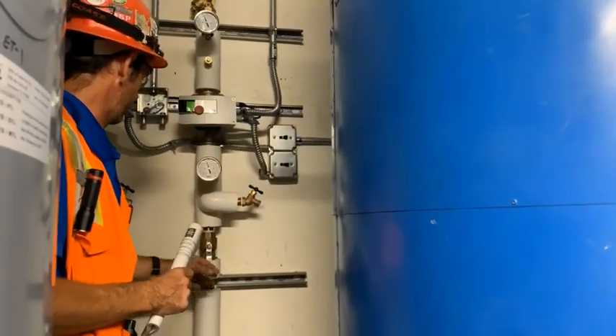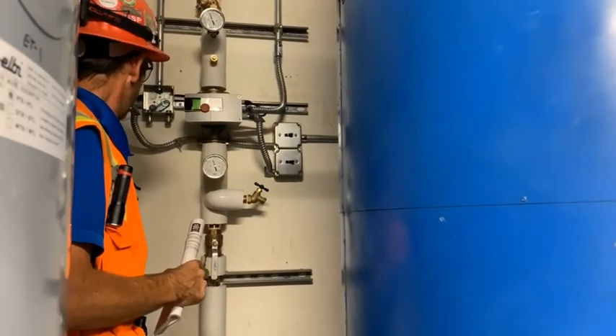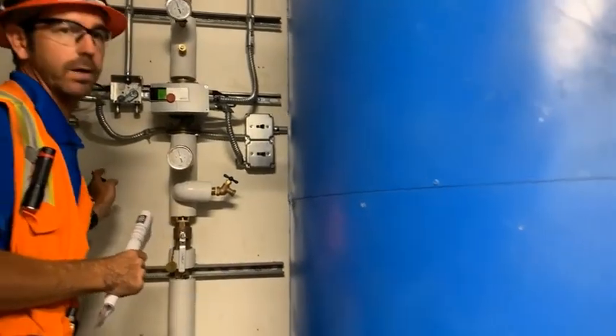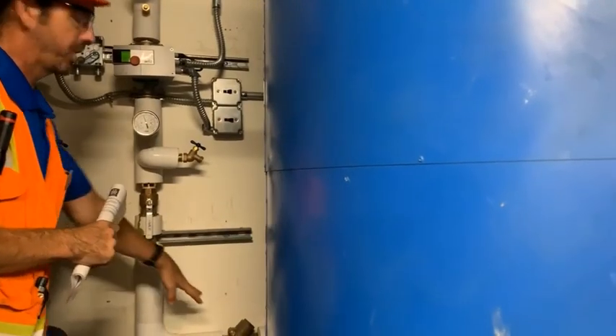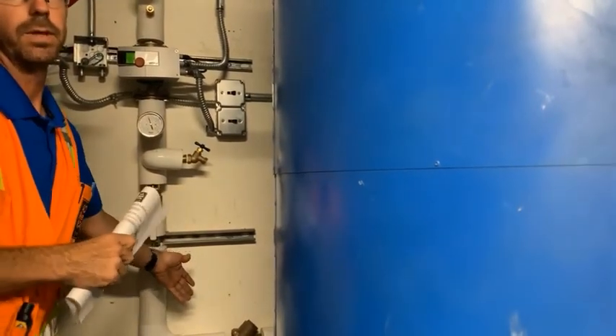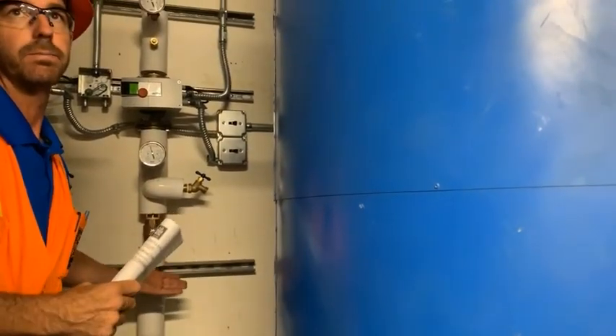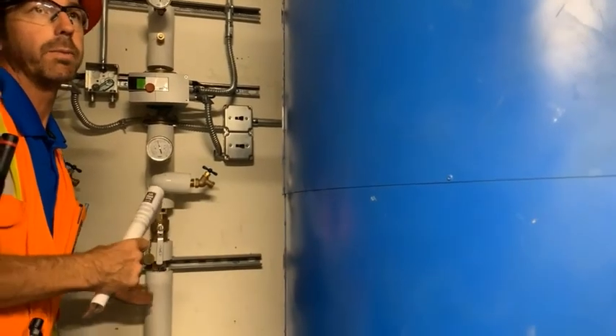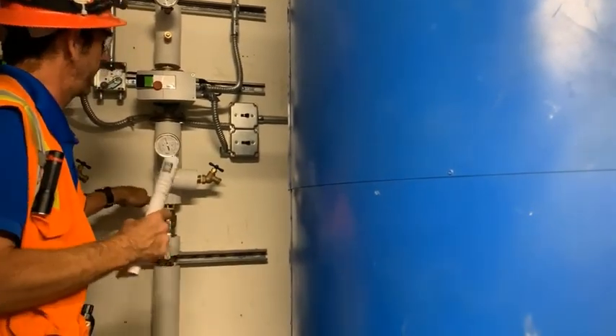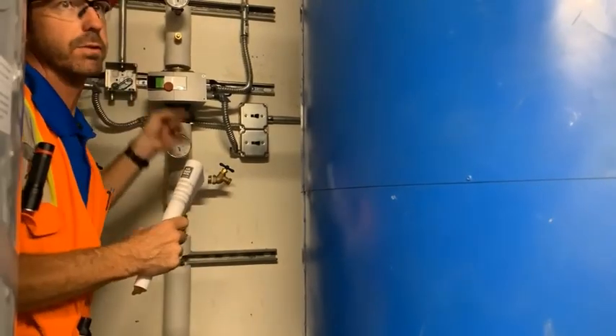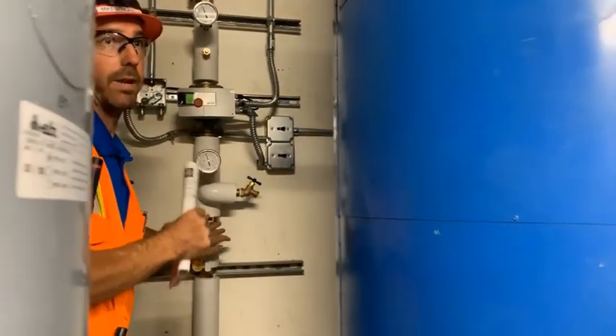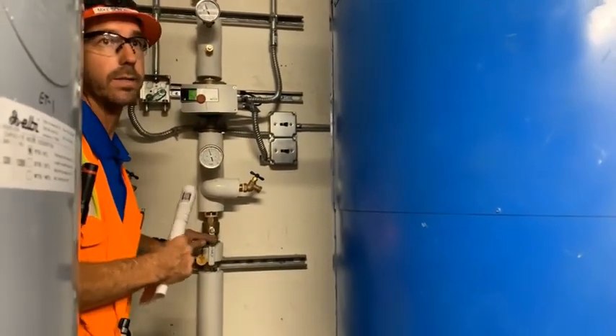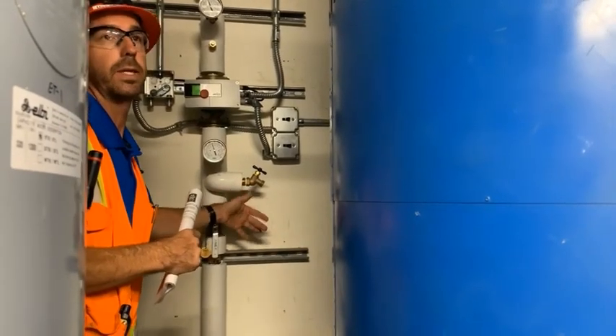And then what I would do is I would shut the valve; you could choose one or the other, it doesn't matter. There are check valves leaving, but they're gravity check valves, they're mechanical devices, okay? They're holding, but I'd shut the valve. That way you know for sure you're drawing the water through the system, okay? Since this is the end of the return and the shutoff valve is below it, it's awesome because you can bleed that out.